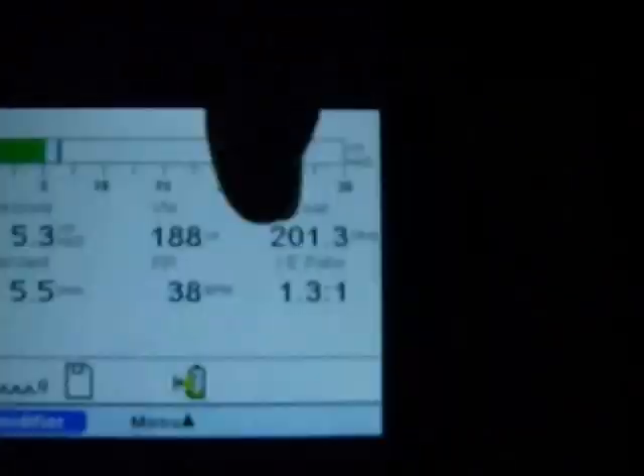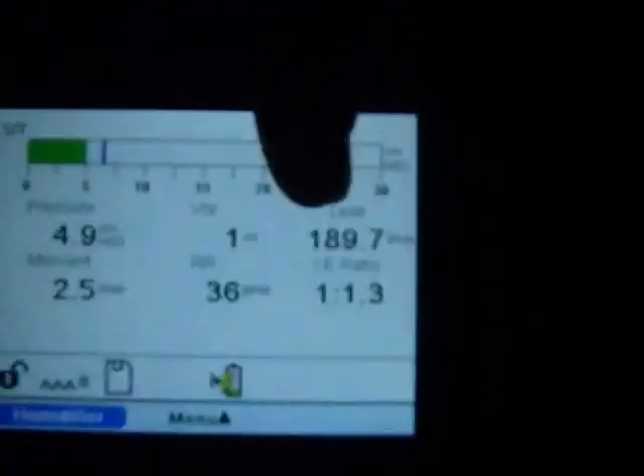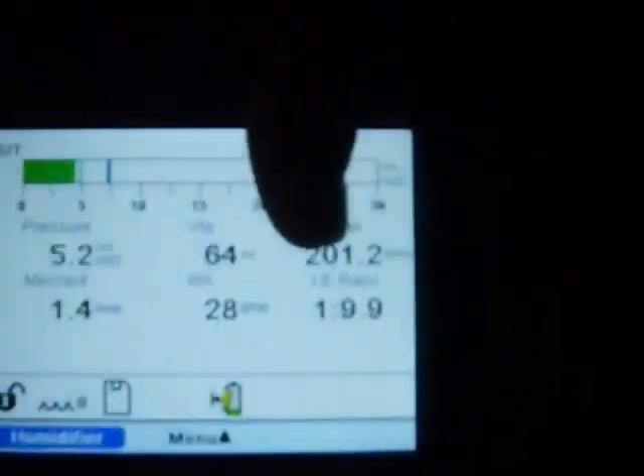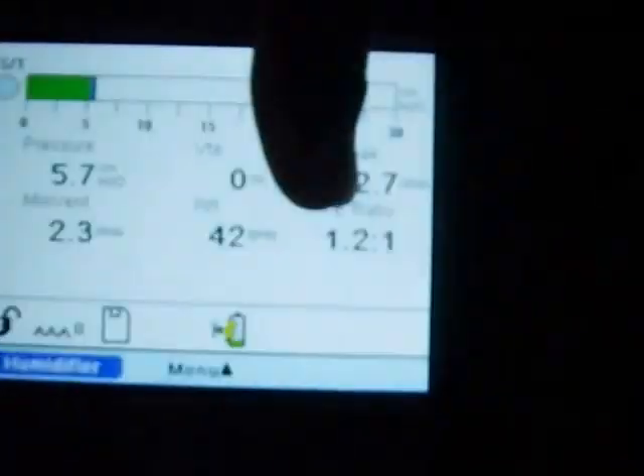And this is the leak you need to monitor, because right now I'm not wearing the mask. You can see excessive leak. Normally this machine, Philips Respironics BiPAP A40, can compensate the leak up to 200 liters. But I would tell you, if you want the machine to perform optimally, you need to monitor the leak to make it less than 60 liters. Then the machine can compensate your leak and can detect when you want to inhale and exhale very well. And there's an I:E ratio. This indicates your inhale time and exhale time in ratio.